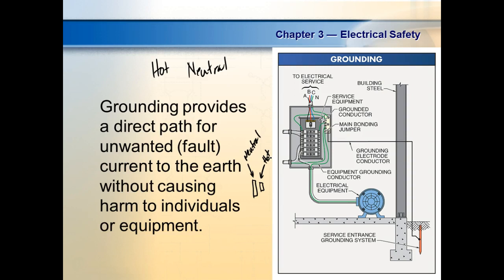If you ground the frame of this unit, and one of the hot leads, even on 3-phase, somehow gets in contact with this metal chassis, it's going to trip your overcurrent protection device. Our two primary overcurrent protection devices are fuses and circuit breakers.